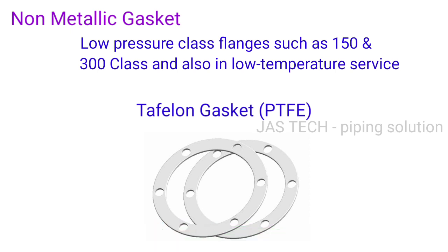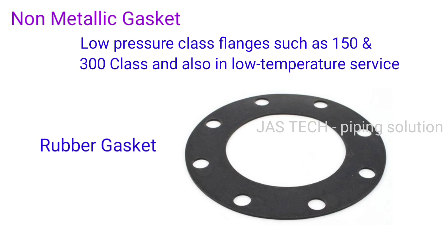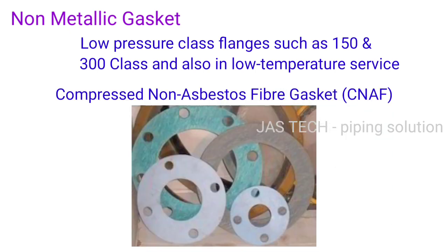Non-metallic gasket: Used for low pressure flanges such as Class 150 and Class 300, and also for low temperature service. Examples include: PTFE gasket (Teflon gasket), rubber gasket, and CNAF gasket (Compressed Non-Asbestos Fiber gasket).